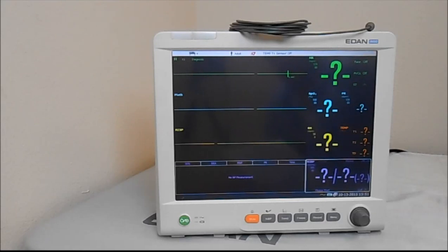This is a skin temp sensor, and it provides temperatures from the skin or the surface of the patient. Simply place the metallic face of the sensor on the surface of the patient and place medical tape to keep it in place. The sensor uses a semiconductor to calculate the reading, so as a result, it'll take approximately 5 minutes before the monitor gives a stable reading. Because the sampling methodology is external, readings will not be as precise when compared to an internal temperature sensor.